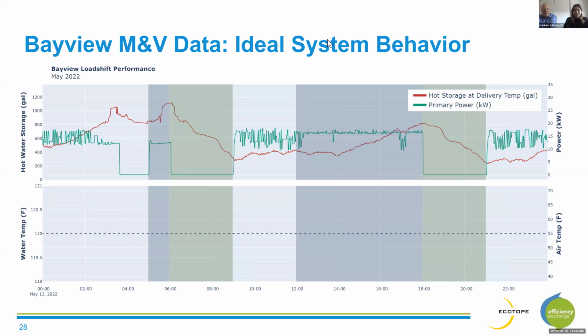And then the next data point we'll look at is power into our primary heat pump. So the goal here is to have 0 power input during the entire shed period. You will see some oscillations here. That just indicates the heat pump is on, and then if we're flatlining at 0, that indicates the heat pump is off. So as we enter our morning load up period, the system was previously off, and this is because the system had adequate hot water storage.